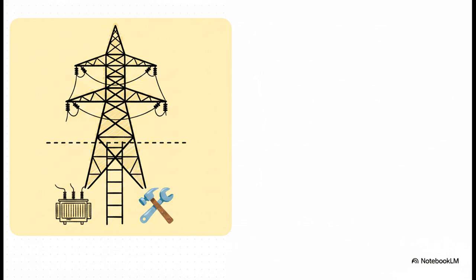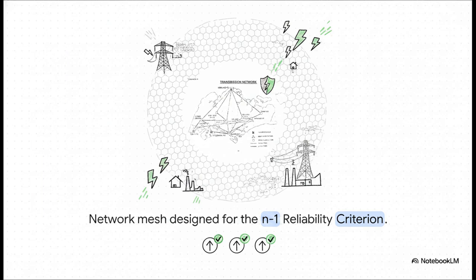Because 6.6 kilovolts is medium voltage, it maps directly onto their operational boundaries. The EMA runs the energy management system for the transmission network, so that's 66 kilovolts and above. But anything 22 kilovolts and below, that falls squarely into SP Group's 24/7 distribution territory. So that 6.6 kilovolt fault is totally their legal responsibility to physically fix, not the EMA's. Now that we know who runs what, let's talk about the physical backbone of the extra high and high voltage tiers. This entire transmission system is heavily meshed and engineered around a principle called the N-1 single contingency criterion. Basically, that means the network is deliberately designed to survive the sudden, unexpected loss of any single generator, circuit, or transformer. The result? Zero cascading failures, zero instability, and zero load shedding. It's essentially an incredibly robust insurance policy against blackouts.